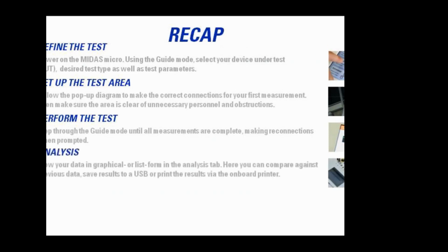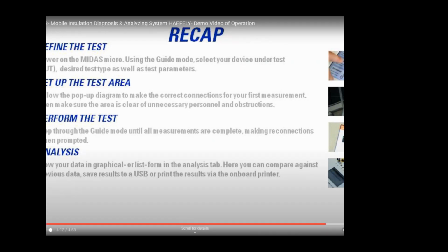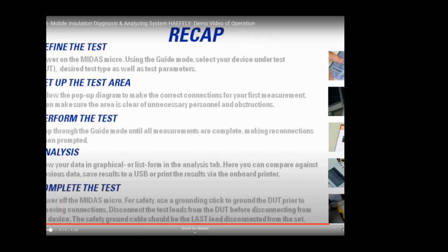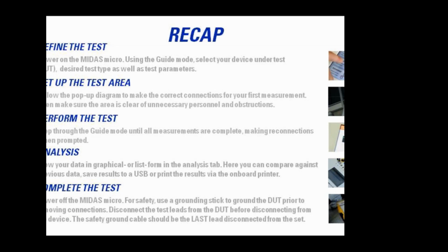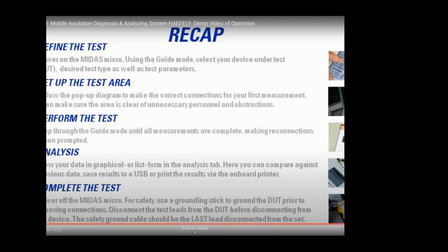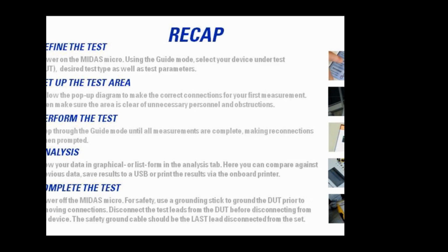Analysis. View your data in graphical or numerical form in the Analysis tab. Here you can compare against previous data, save the results via USB, or print the results via the onboard printer. Complete the test. Power off the MIDAS Micro. For safety, use a grounding stick to discharge the device under test prior to removing connections. Disconnect all test leads from the DUT before disconnecting from the MIDAS Micro. The safety ground cables should be the last leads disconnected from the unit.